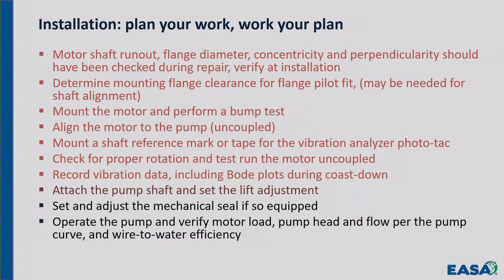Let's see. Then you attach it to the pump shaft and you set the lift. We'll talk about that. If you have a mechanical seal on the pump, okay, when you're setting the lift adjustment, you're moving the shaft up and down, you can't have your mechanical seal locked in. That seal's got to be loose. When you're doing the alignment, you may be moving the shaft side to side or things. That seal's got to be protected so you don't damage that seal. If you got packing, it's no problem.